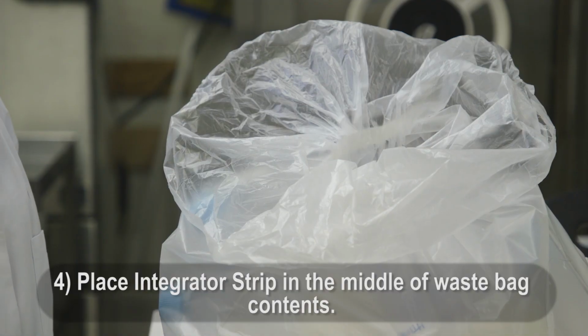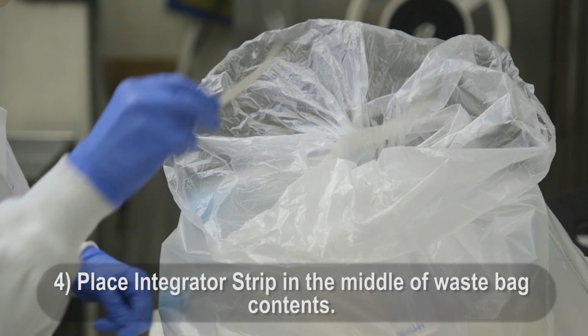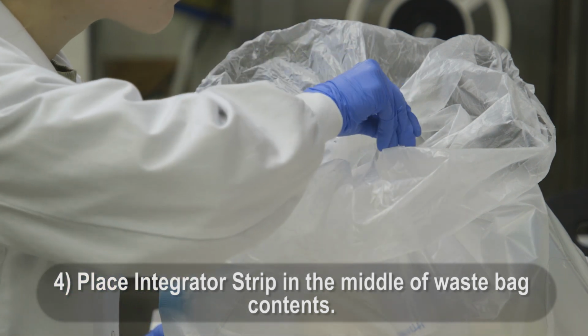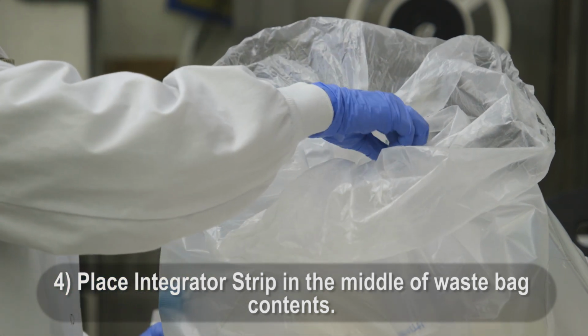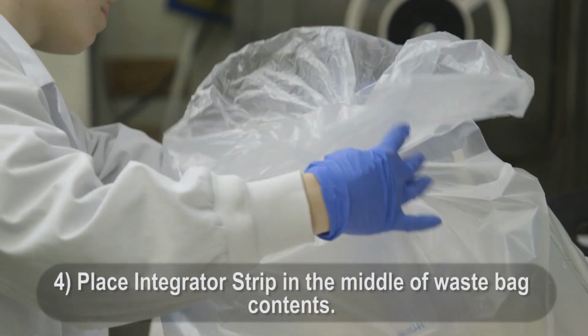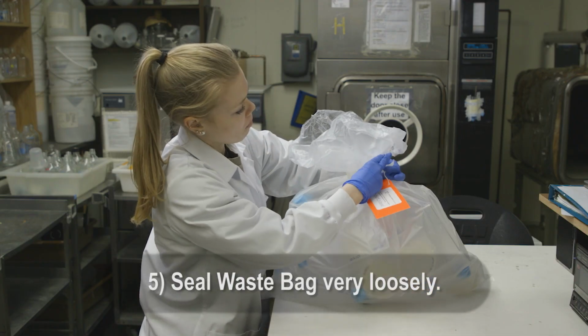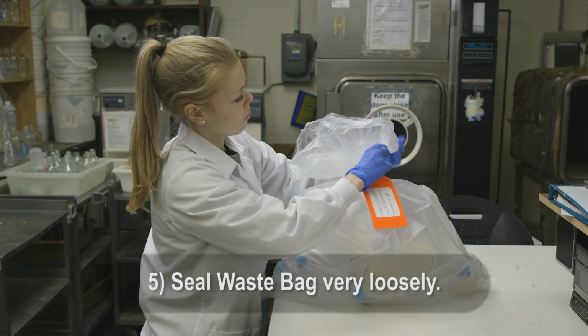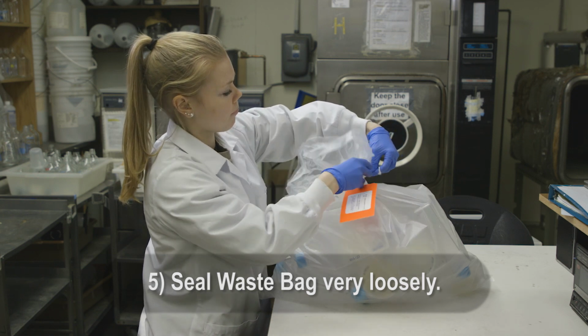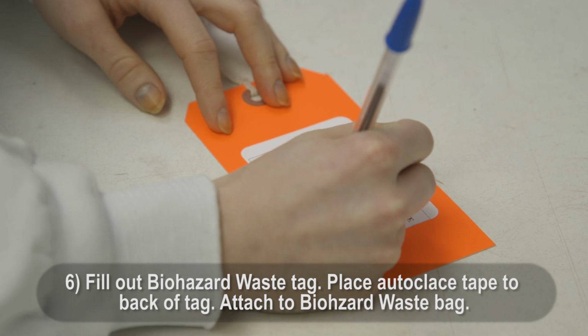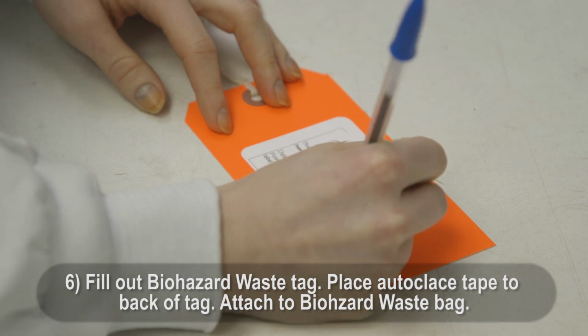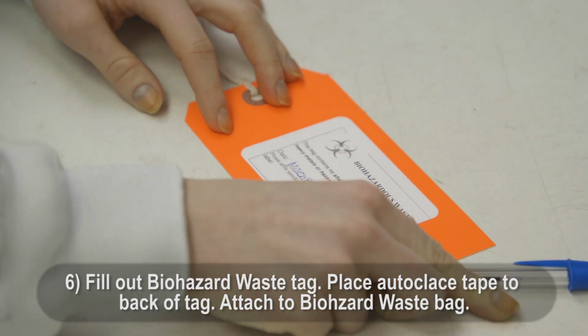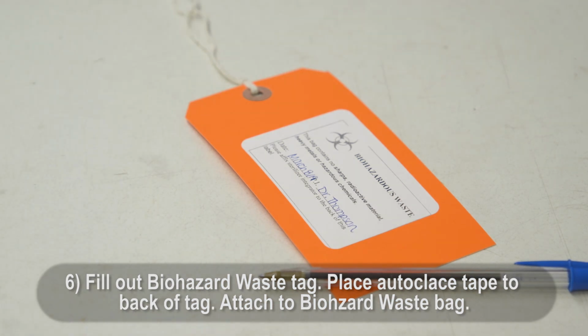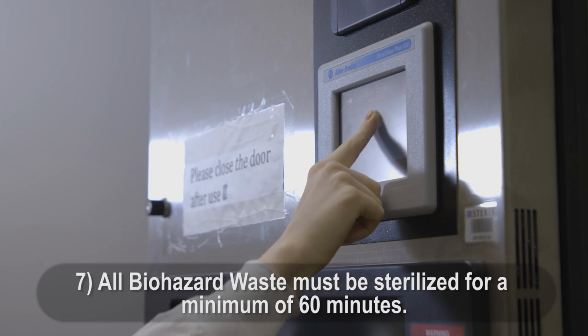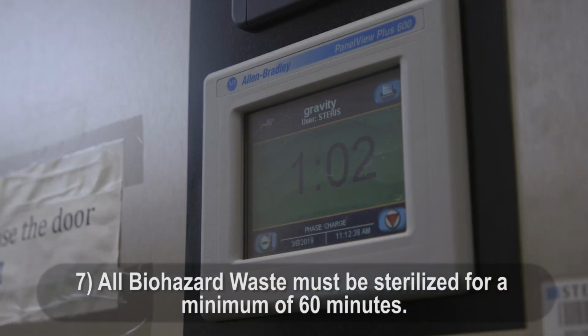4. Place a chemical integrator strip in the middle of your bag's contents. This will allow you to determine if steam was able to penetrate to the center of the bag contents. 5. Make sure to seal the biohazard waste bag very loosely. Steam must be able to get inside the bag. 6. Fill out and attach the biohazard waste tag to the bag. Place a piece of autoclave tape on the back of the biohazard waste tag. 7. All biohazard waste must be sterilized for a minimum of 60 minutes.